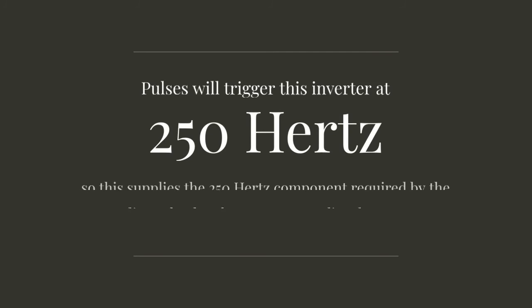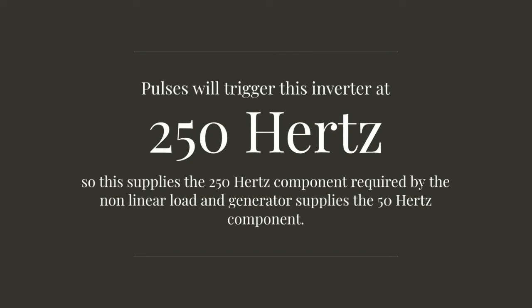So this is shunt active filter. If non-linear load requires fifth harmonic the frequency is 5 into 50, 250 hertz. So I will trigger this inverter at 250 hertz. So this supplies the 250 hertz component required by the non-linear load and generator supplies the 50 hertz component.